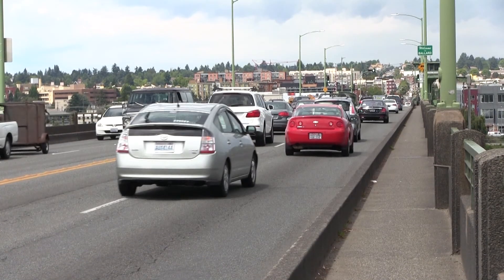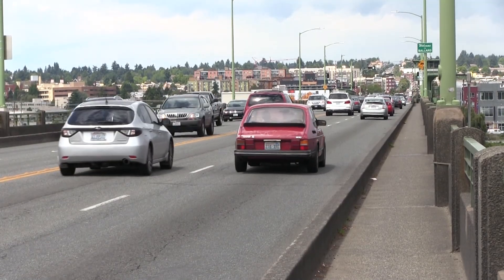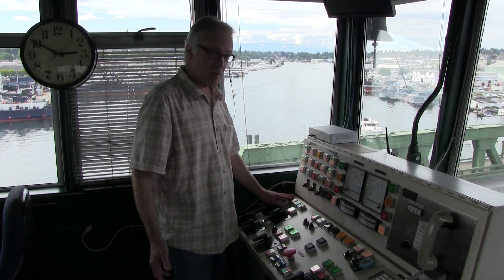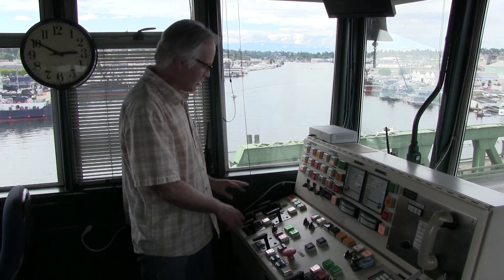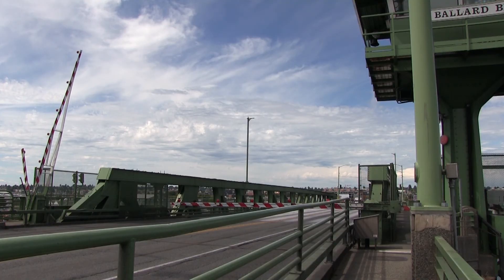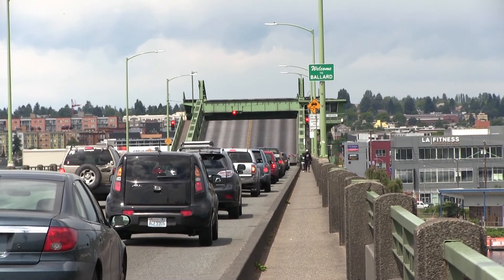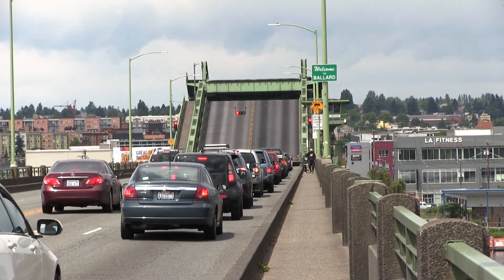Here at the busy Ballard Bridge, bridge operator Dave Gleisk shows us how the bridge opening works. When I want to start the opening, I make sure the key is turned on and then I press the red button, which initiates a ten-second delay before I can operate the gates. The gate sequence is the same on each bridge — you put the far side gate down first, then the oncoming gates, to make sure all cars are stopped. This accounts for safety in case of a power outage. Everything is in sequence and interlocked for safety.